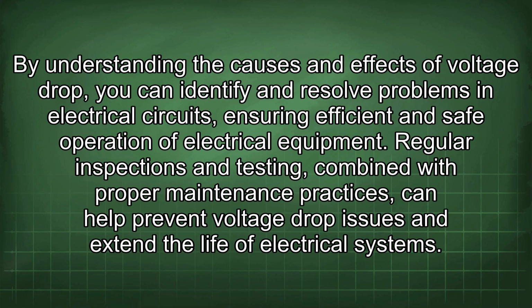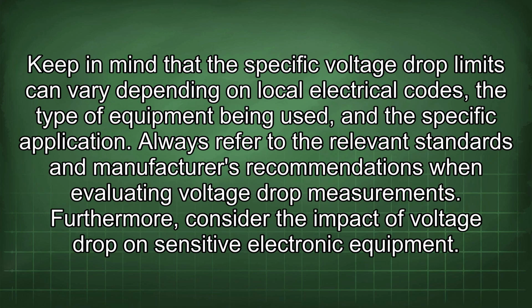Regular inspections and testing, combined with proper maintenance practices, can help prevent voltage drop issues and extend the life of electrical systems. Keep in mind that the specific voltage drop limits can vary depending on local electrical codes, the type of equipment being used, and the specific application. Always refer to the relevant standards and manufacturer's recommendations when evaluating voltage drop measurements.